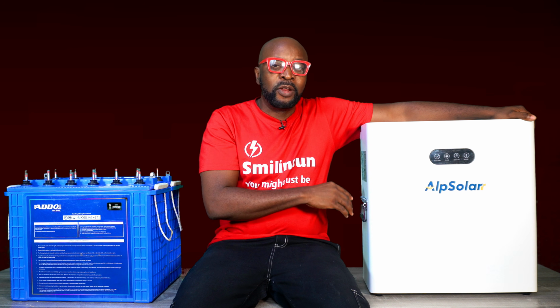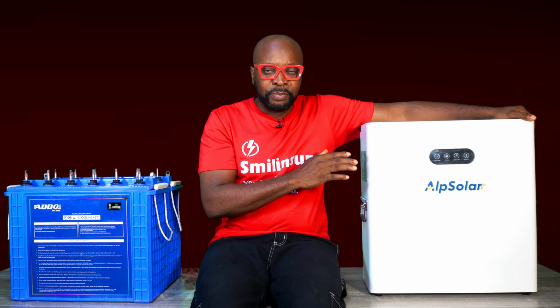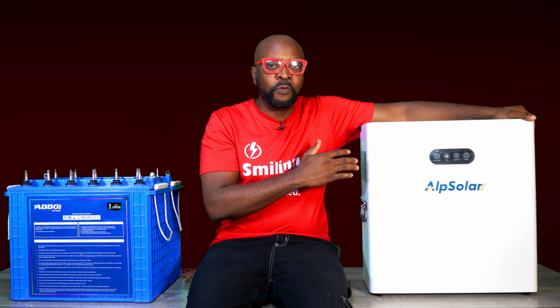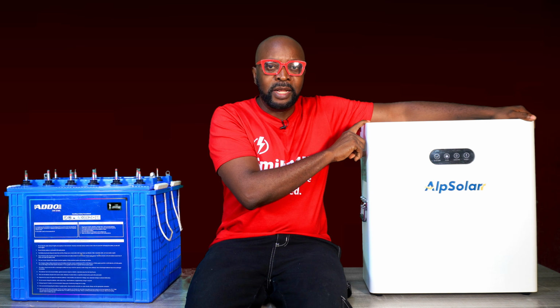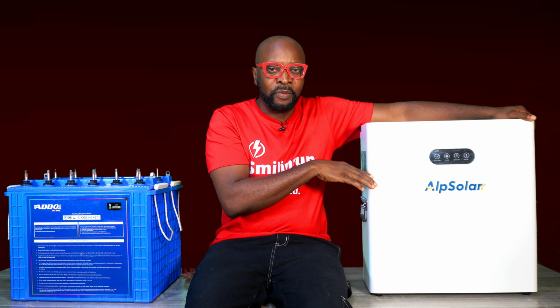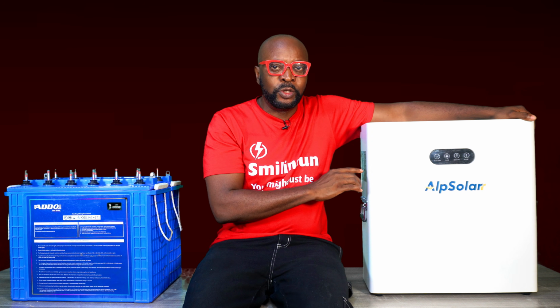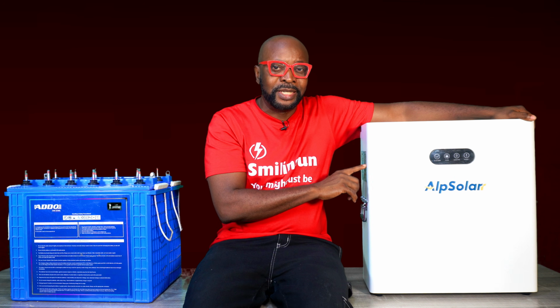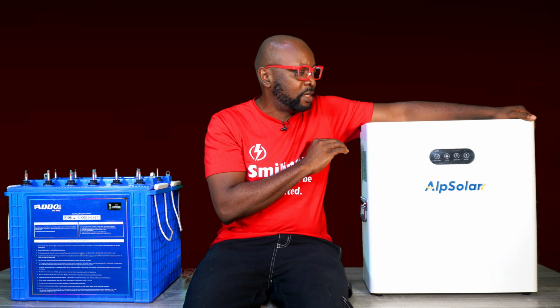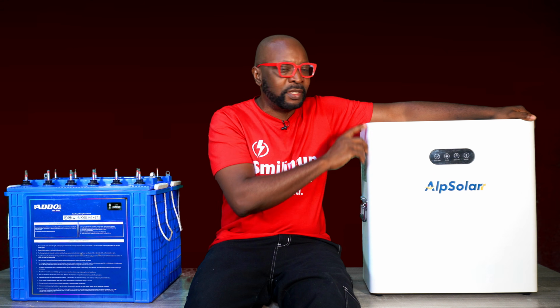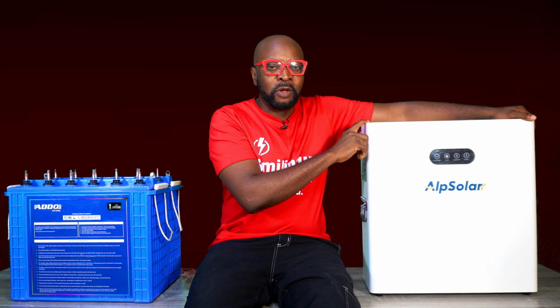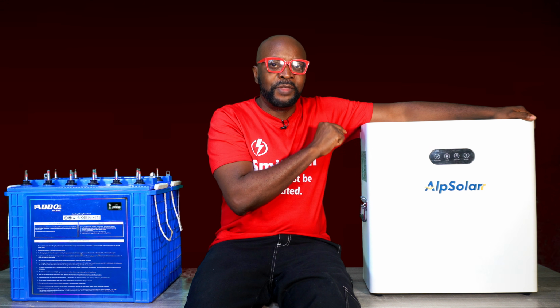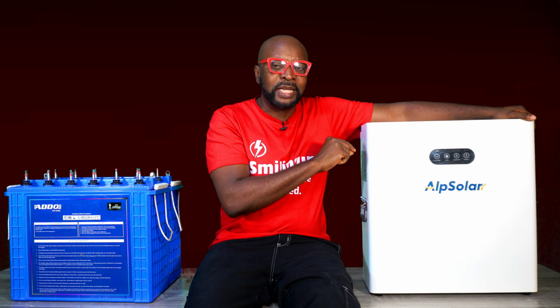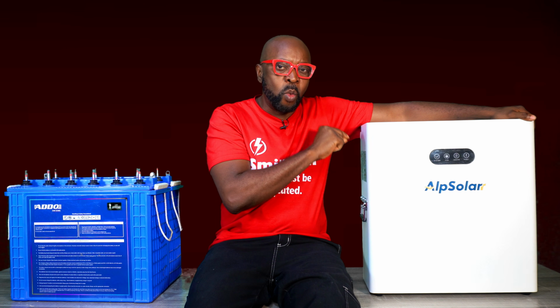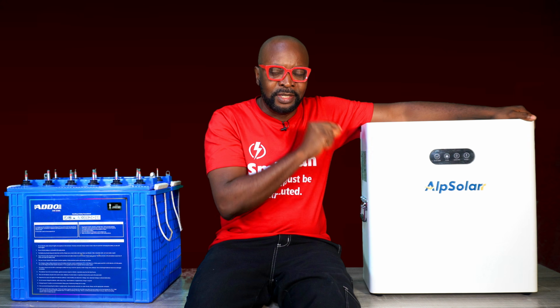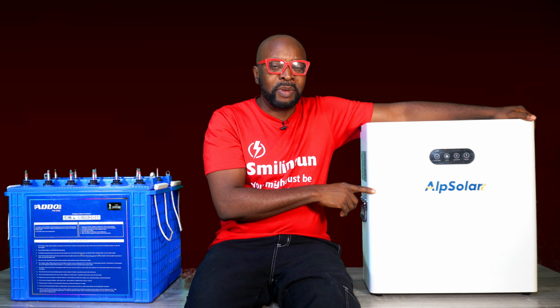It also manages the temperature. If the temperature rises above what is recommended for the cells of the battery, it's going to shut down. It also ensures that all the individual cells of the battery are charging and discharging at the same current. You have 16 battery cells in this battery. It is the function of the BMS to ensure that every single one of them is charging with the same amount of voltage and the same amount of current, both when the battery is charging and when it is discharging. That's the function of the battery management system.